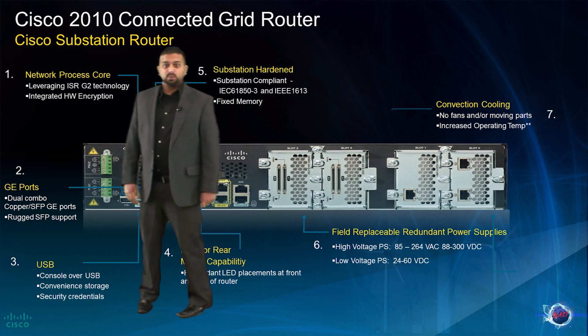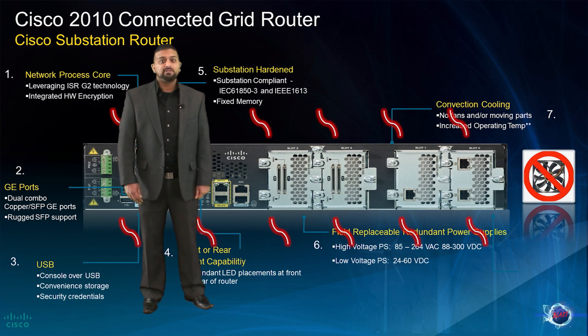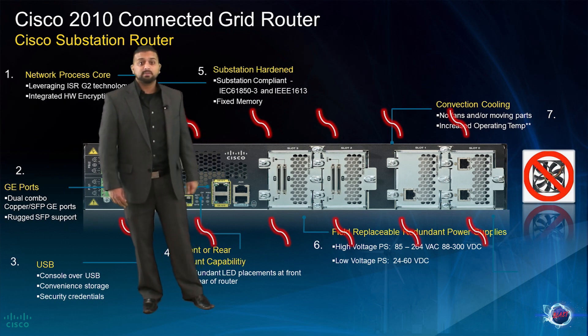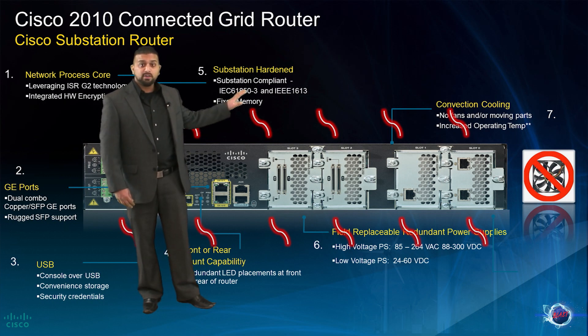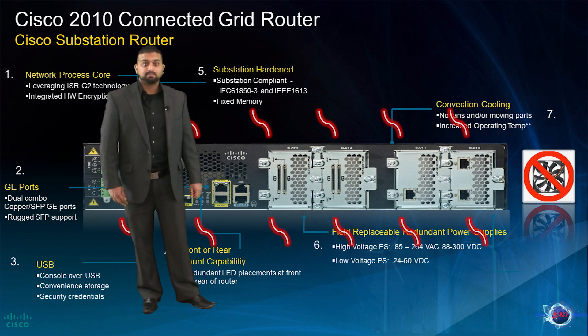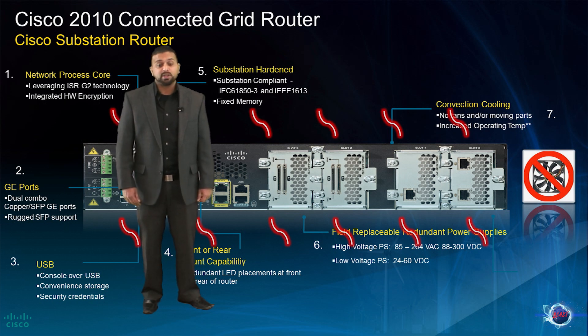Because of the harsh environments the CGR 2010 will be deployed in, and in order to comply with the IEC 61850 and IEEE 1613 standards, the CGR 2010 platform has no moving parts such as fans, in order to protect the unit from mechanical failure. Airflow is achieved through convection cooling. Because of this, it's important that units are deployed with one rack unit of space above and below. In addition, the operating temperatures were increased to comply with substation compliance standards.